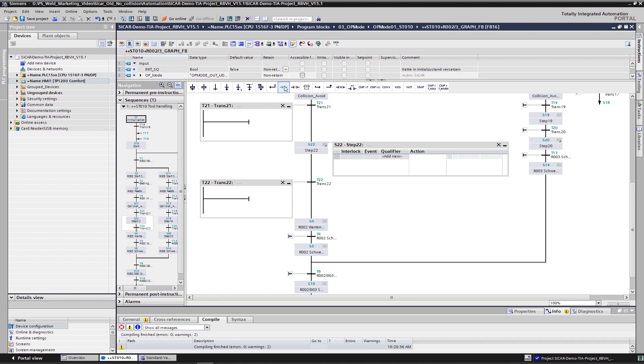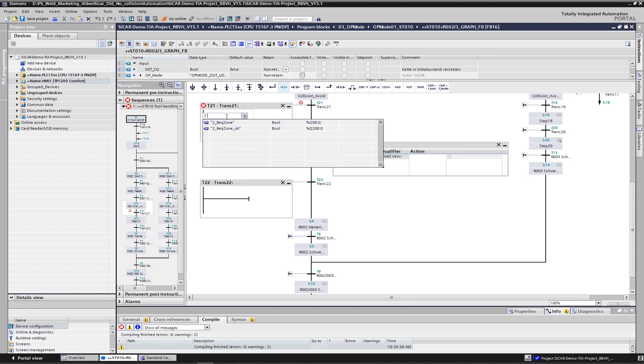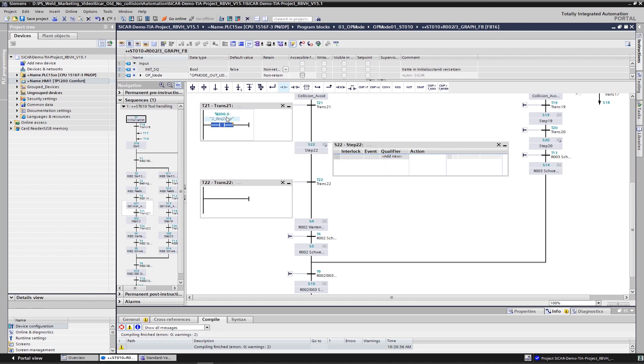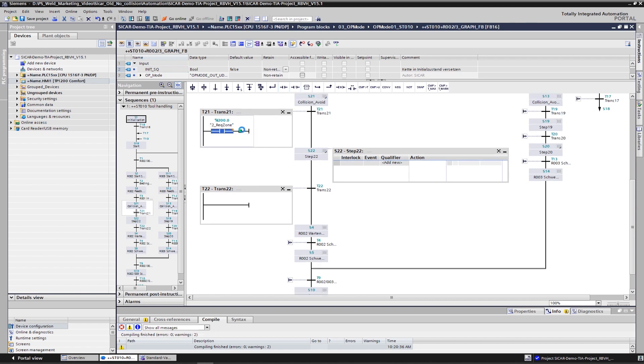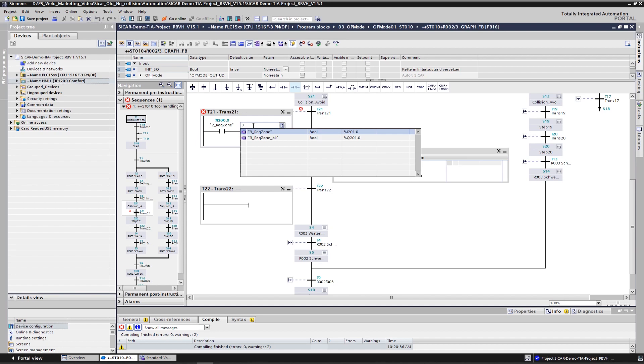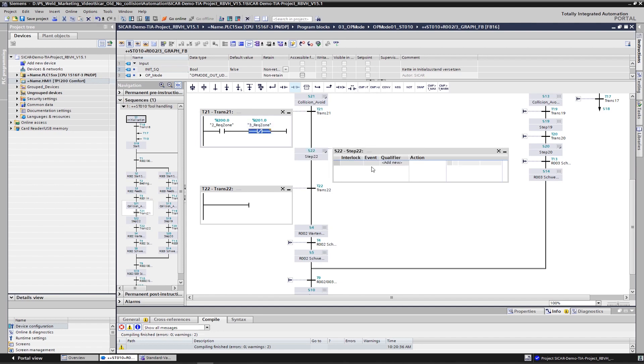In the transition shown, we ask whether the zone of one robot is occupied and the zone of the other robot is clear, that means not occupied. So far, quite logical. Next, we'll define the action in our graph sequence chain, in other words, what to do when the transition is fulfilled.